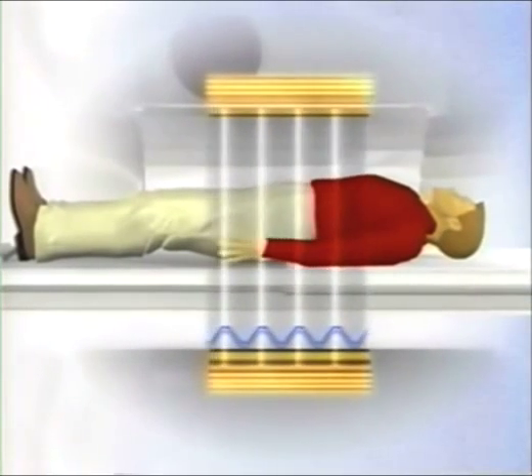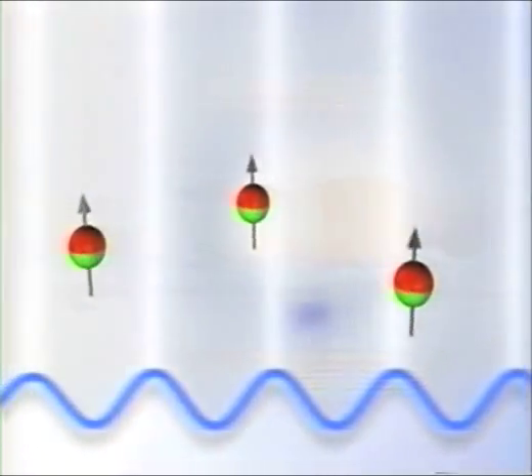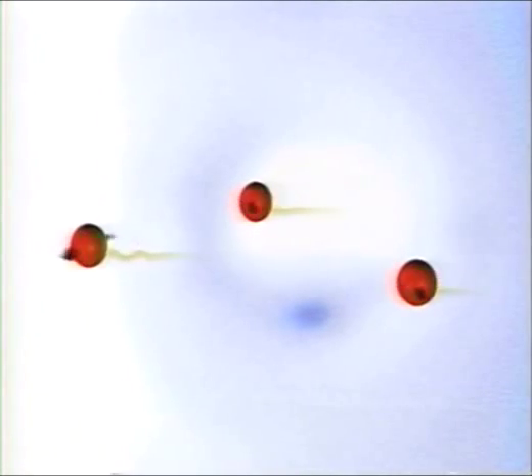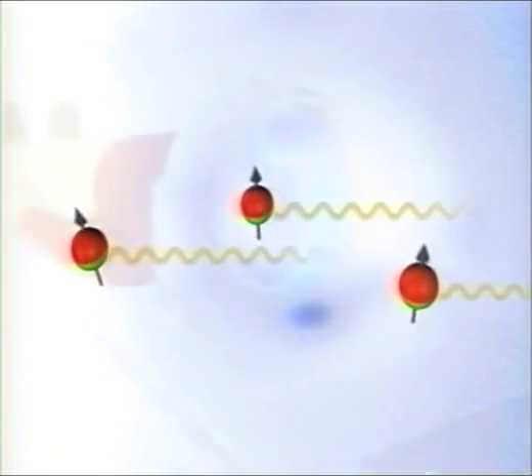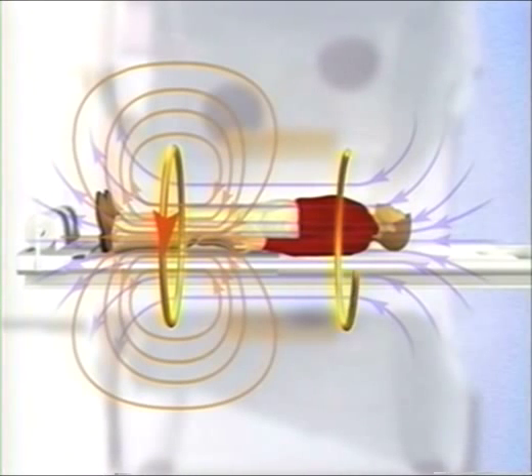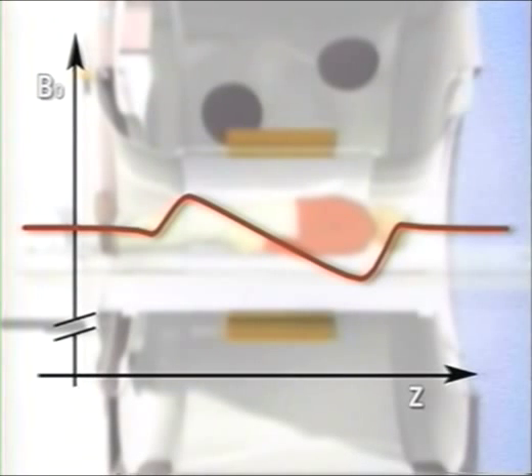A transmitting coil in the magnet generates the alternating magnetic field in the area under examination. After being excited by high-frequency energy, the atomic nuclei return to the equilibrium position parallel to the static main magnetic field. The atomic nuclei then emit electromagnetic waves in the frequency range at which they were excited. Receiver coils arranged around the patient detect these weak RF signals. During excitation and while the nuclei are returning to the steady state, spatially varying magnetic fields known as gradient fields are switched on so that the resonance frequency of the nuclei varies from one region of the patient to the next. This is how the spatial distribution of the atomic nuclei in the patient is coded into MR signals.